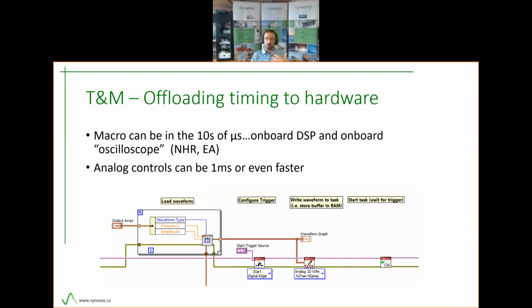The second option I mentioned is the analog controls, and that offers very similar benefits. If you have a good DAC, such as an NI DAC, you can simply load a large array of points in memory and let the hardware play it on the analog output to modify the various set points. When using this method with a module such as the 9264 or 9265 analog outputs, you get the added benefit that all the data played and recorded is on the same clock. Control and readbacks can be compared with microsecond accuracy across multiple instruments and multiple sensors because the readings and the controls are processed by a single box.